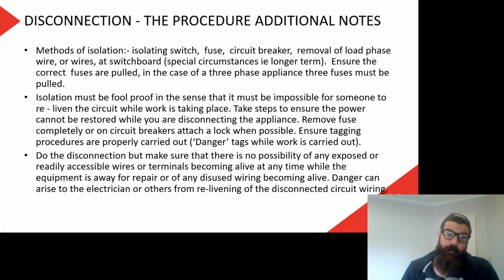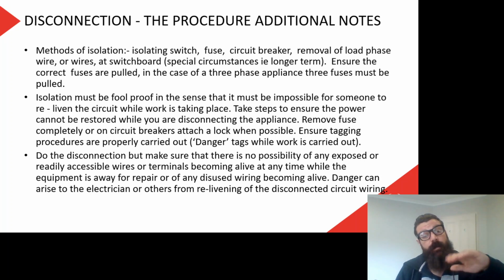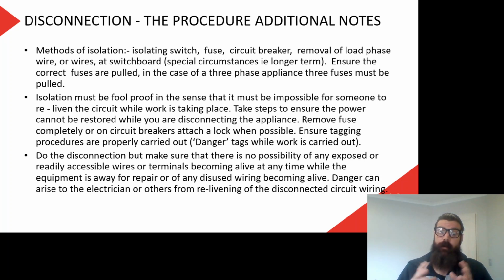We must ensure that the correct fuses are pulled, and in the case of a three-phase appliance, 3 fuses must be pulled. So usually with a three-phase circuit breaker, it'll be one switch that will disconnect all 3 phases. But if it's protected by fuses, then we're going to have 1 fuse for each phase, and in that case we need to make sure we get all 3 of those fuses. It's usually fairly straightforward that the 3 fuses will be together for each specific circuit. So it's not like 3 random fuses located around the switchboard.